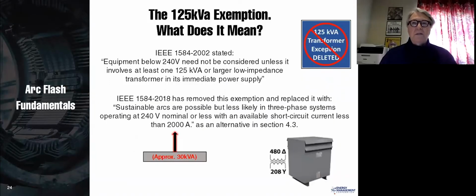All right, this is the 125 kVA exemption. Now, what does that mean? In the IEEE 1584-2002, it stated, equipment below 240 volts need not be considered unless it involves at least 125 kVA or larger low impedance transformer in its immediate power supply.